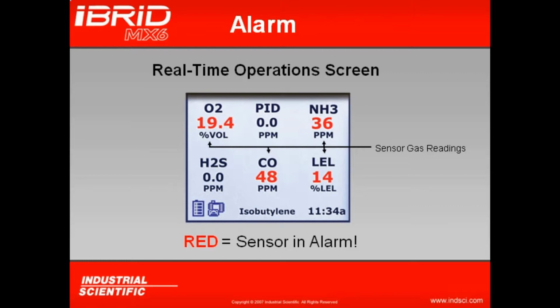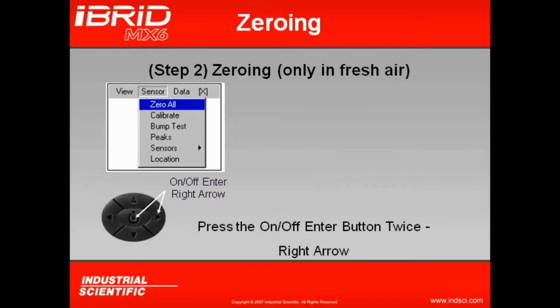Any gas reading that appears on the instrument's display in red is going to be an indication that that particular sensor is in alarm. Not only will the gas reading be red, but it's also going to increase in font to give us a visual indication that that particular sensor is in alarm.